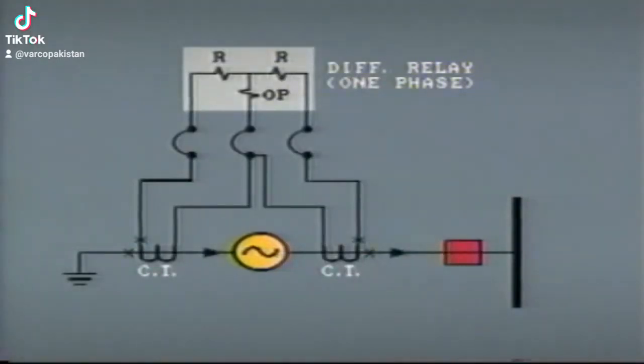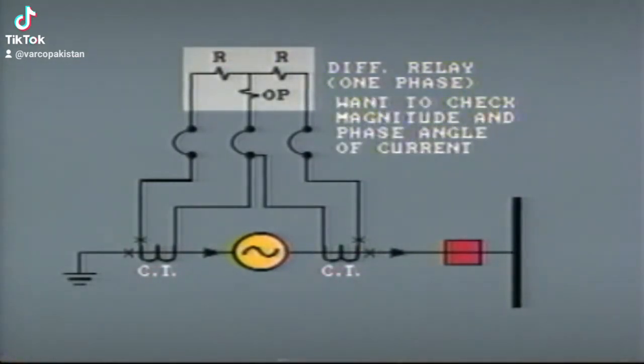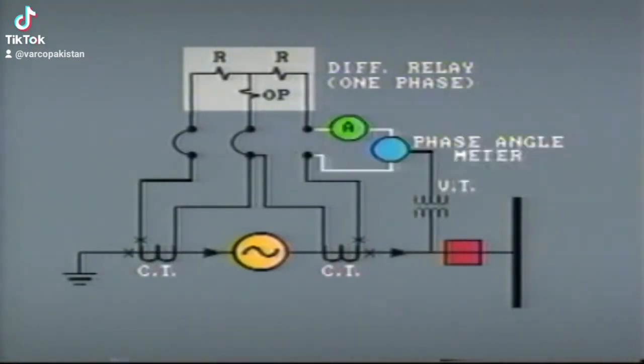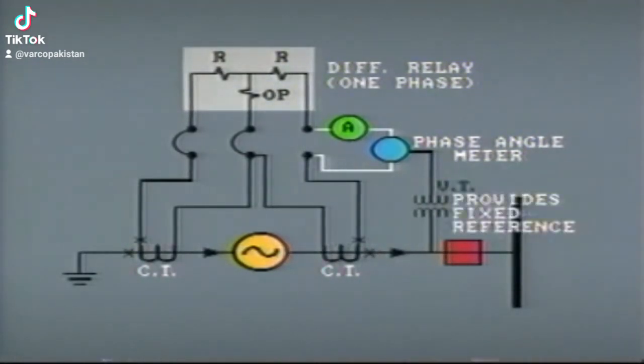As an example, let's look at in-service readings of the generator differential protection taken at the relay panel. Our objective is to test the magnitude and phase angle of current in each of the restraining coils and operating coils. A suitable ammeter and phase angle meter are connected to the circuit under test through the test board. The phase angle meter must be provided with a fixed voltage which can be used as reference in order to determine the phase angle and consequent direction of current.